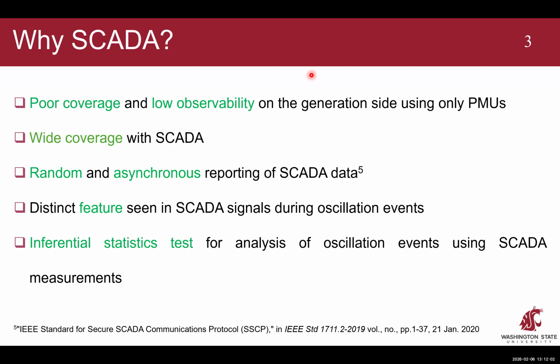Now, the trick, and what helps the analysis of how we can use SCADA, is that the SCADA scan or SCADA polling is done in an asynchronous fashion. And they are not synchronized. And in fact, if you look at two consecutive SCADA measurements coming from the same RTU, the time gap between them will not be the same, because this is based on the polling schedule, how the RTU monitors or measures the signal, and the communication delay between the RTU and the control center. So this is kind of random, and this is well known, and that's what we exploit in our method. So if we think of an oscillation, and I will show some pictures shortly, what we observe is that the SCADA observation of that oscillation can fall anywhere on the waveform.